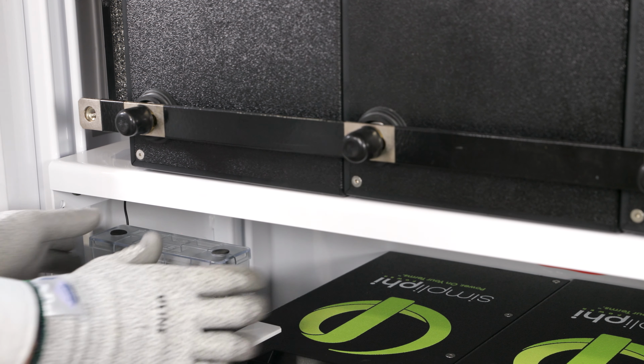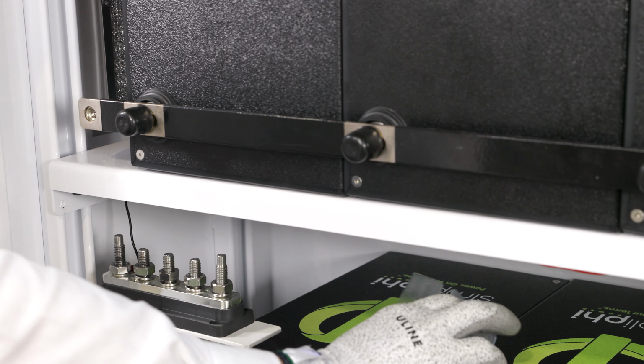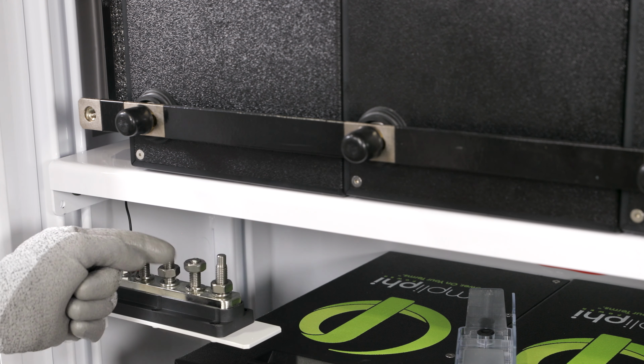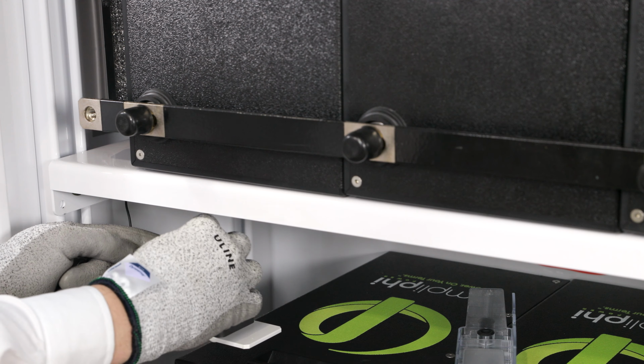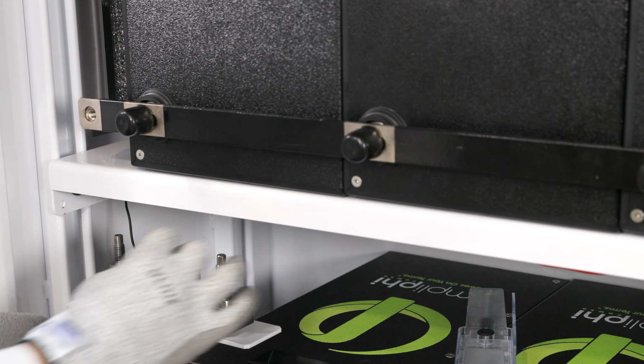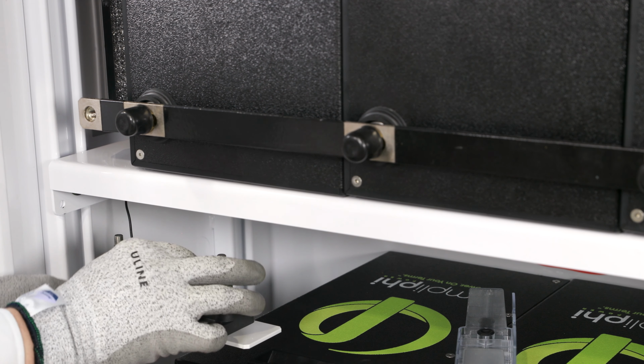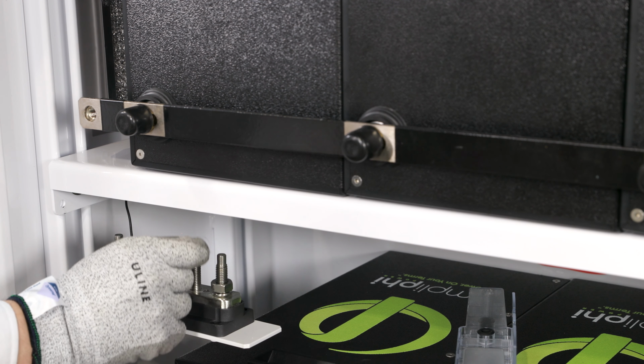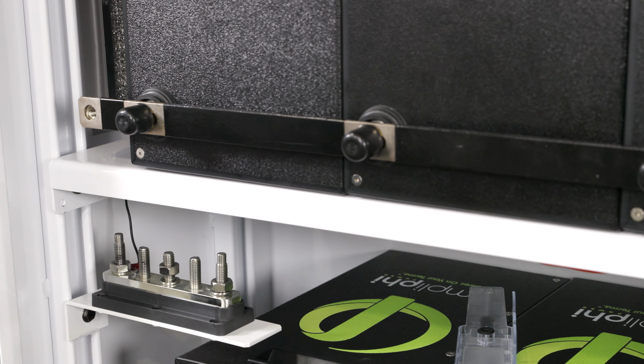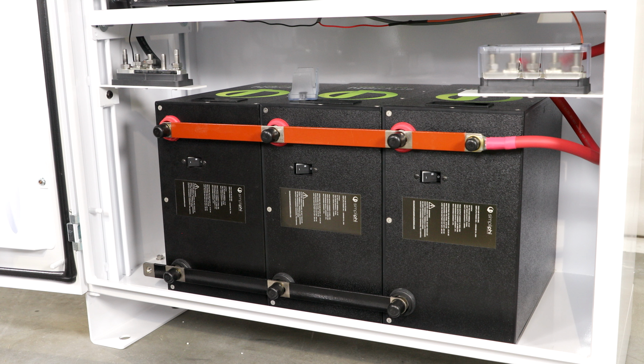Remove the plastic 5-point terminal block cover by lifting. Remove the nut and lock washer from the 5-point terminal block. We will be landing the bottom shelf negative bus bar to the terminal block post, second in from the right. Connect the 2-aught cable to the bus bar using the included 3/8 inch brass hex head cap screw.